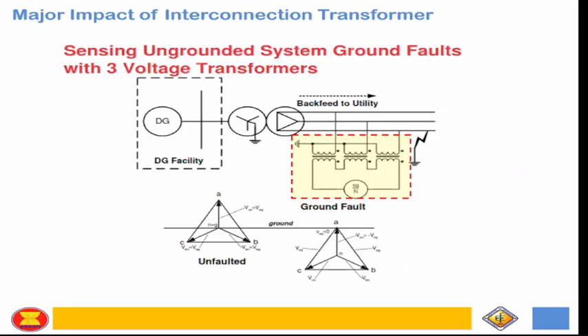Okay? And then, what would be the appropriate protection? Because there's no zero sequence current on that time. So kung magkaka-fault dito, okay? Since this is delta, no circulation of zero sequence current for this scenario. So yung overcurrent protection mga yon is not effective anymore. Okay? The appropriate protection for that is the 3V0, which monitors the voltages, the phases, and then the vectorial sum of that, yun yung magiging sensitivity mo. Okay? Yun yung mga quantities na titingnan mo: the zero sequence voltage protection or the 3V0. Okay? That's for the ungrounded system protection.